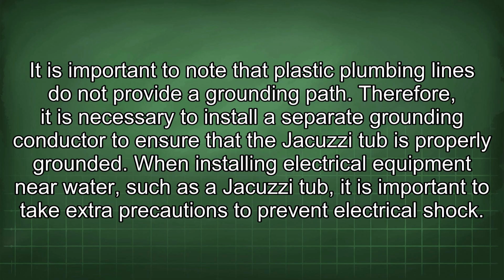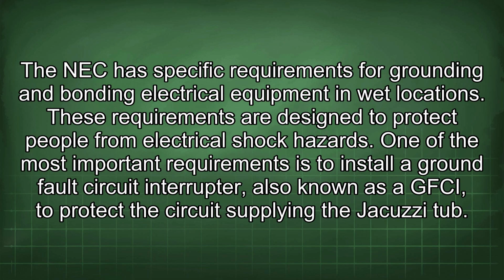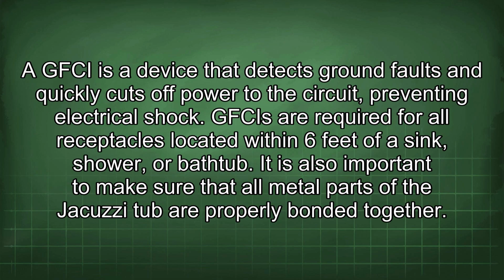When installing electrical equipment near water, such as a jacuzzi tub, it is important to take extra precautions to prevent electrical shock. The NEC has specific requirements for grounding and bonding electrical equipment in wet locations. These requirements are designed to protect people from electrical shock hazards. One of the most important requirements is to install a ground fault circuit interrupter, also known as a GFCI, to protect the circuit supplying the jacuzzi tub. A GFCI is a device that detects ground faults and quickly cuts off power to the circuit, preventing electrical shock. GFCIs are required for all receptacles located within 6 feet of a sink, shower, or bathtub.